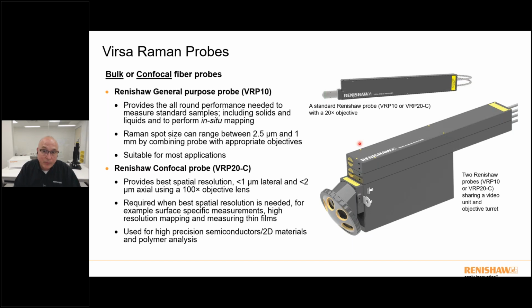We deliver 2 different types of probes. One is going to be intended primarily for bulk analysis. That's the VRP10 or Virsa Raman probe. And then we have another one which is intended primarily for confocal analysis, and that's the 20. And then again, you can still have the video option on these. You'll want to use the VRP20 when doing high confocal work. So if you're thinking about thin films and things like that, then that's a good application for it. Otherwise, the standard bulk probe will do really well on most measurements here.